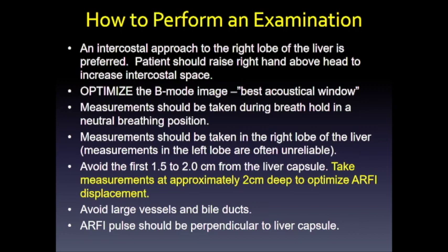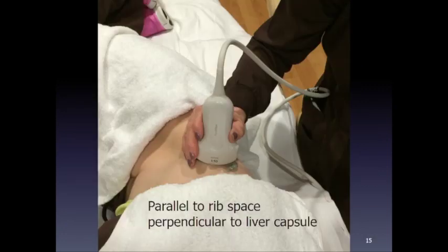Always avoid large blood vessels and bile ducts, as their sharp borders cause refraction of shear waves and interference patterns, giving inaccurate measurements. Research also shows that the transducer should be perpendicular to the liver capsule in both planes — angling the probe causes significant refraction of energy, producing weaker displacements and much more error in measurements, even with small amounts of angulation. Position the transducer parallel to the rib space and perpendicular to the liver capsule.